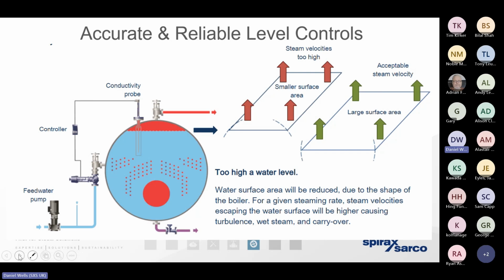Now, we need to remember that there are only certain types of level controls that can hold an accurate and reliable level within the boiler. And that's a capacitance probe. A capacitance probe, for example, can send a signal to a modulating pump, which means we can hold the level of the water within the boiler at an accurate and defined point, meaning that the water coming into the boiler is going to be in equilibrium with the steam that is leaving the boiler. It means we're getting a much, much better condition of steam, far, far drier, with more energy present within it. And it's actually the level controls themselves that send the signal to that modulating pump. Fortunately, the level controls and the modulating pumps can be retro-engineered. So we can improve the sophistication and efficiency of those controls, but leave the original boiler intact.